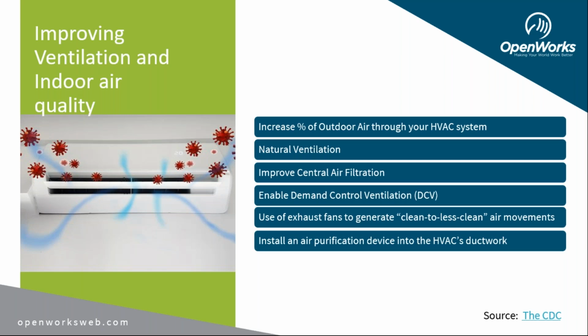or exercise facilities. Effectively, this means if you have an area that is considered to be less clean or is highly occupied, you can use an exhaust fan to remove the air from that part of the building and not let it recirculate throughout the building's main ductwork. Keep in mind, in order to keep the building pressure balanced, you will need makeup air units to replace any air that is removed by an exhaust fan.